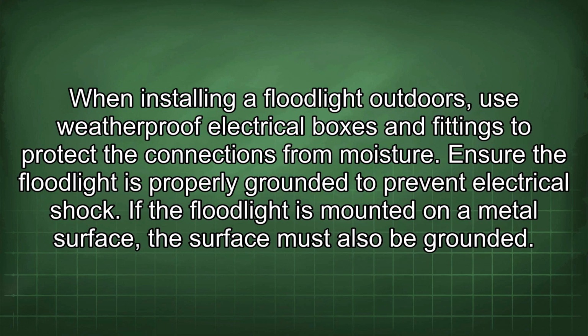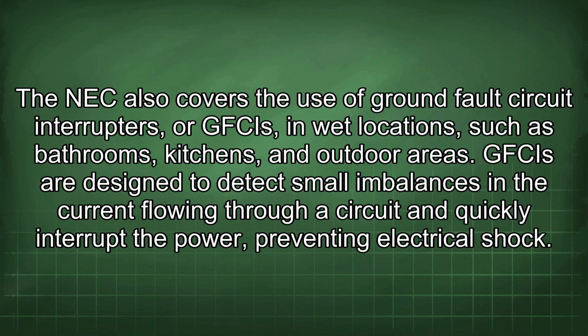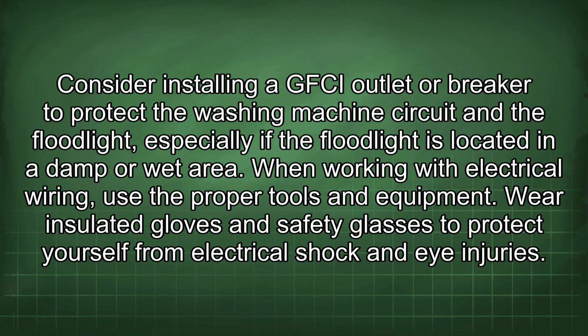When installing a floodlight outdoors, use weatherproof electrical boxes and fittings to protect the connections from moisture. Ensure the floodlight is properly grounded to prevent electrical shock. If the floodlight is mounted on a metal surface, the surface must also be grounded. The NEC also covers the use of ground fault circuit interrupters, or GFCIs, in wet locations such as bathrooms, kitchens, and outdoor areas. GFCIs are designed to detect small imbalances in the current flowing through a circuit and quickly interrupt the power, preventing electrical shock. Consider installing a GFCI outlet or breaker to protect the washing machine circuit and the floodlight, especially if the floodlight is located in a damp or wet area.